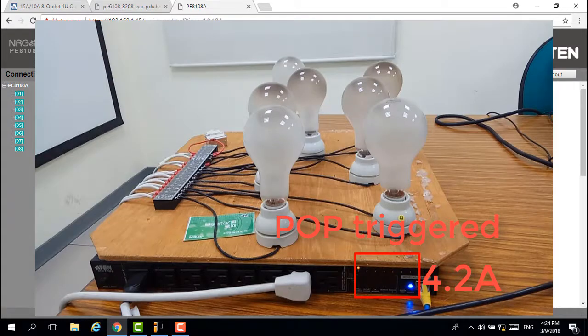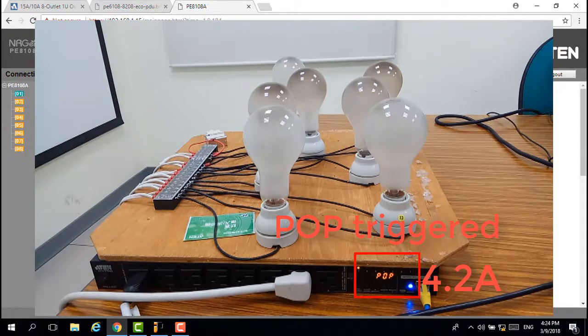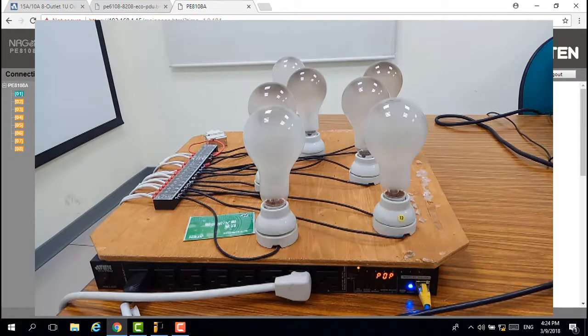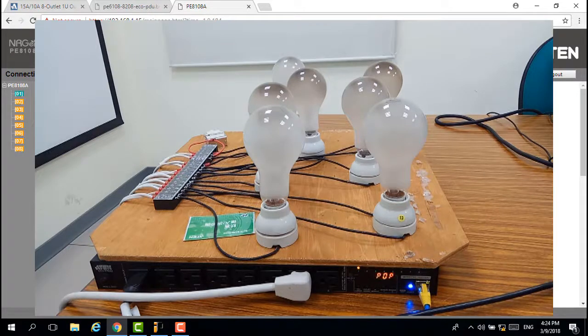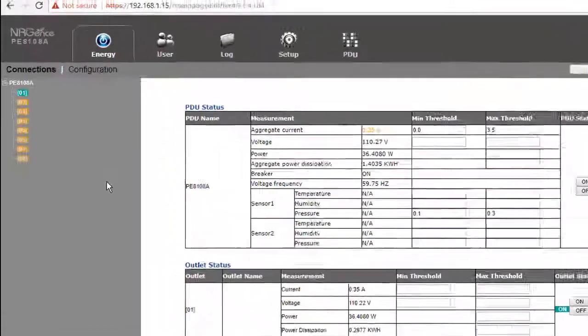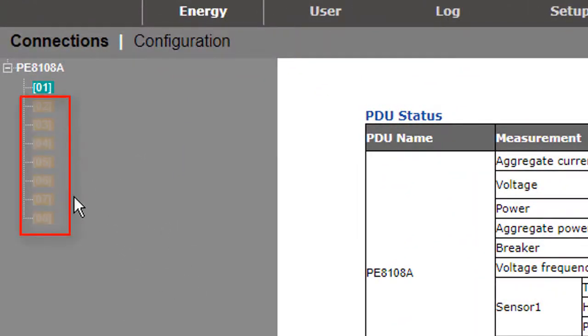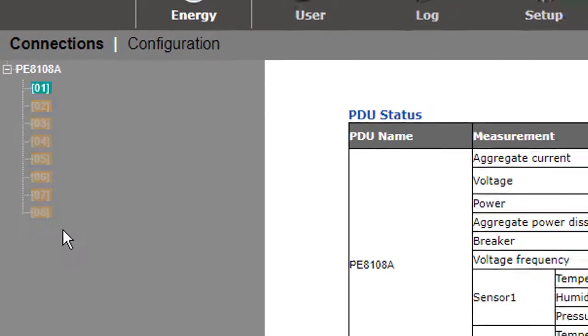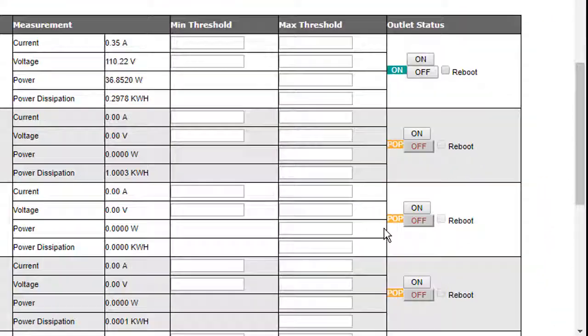Because the power consumption reached the max threshold of 3.5 ampere, you can hear the outlets powering off one by one. Back to the connection page. From outlet 2 to outlet 8, the icon lights orange and shows POP wording.